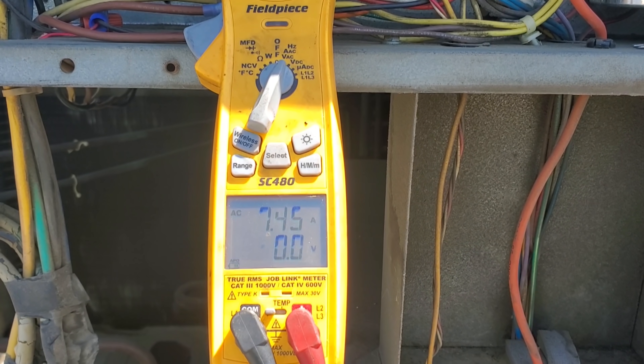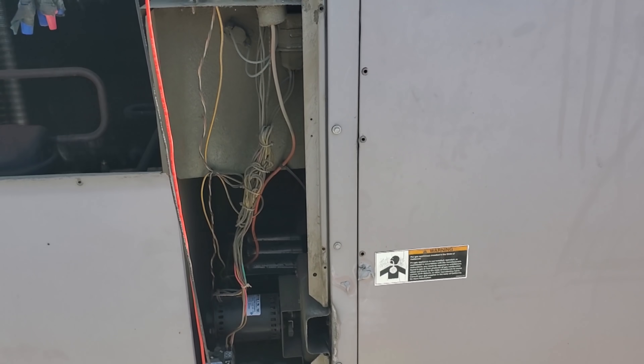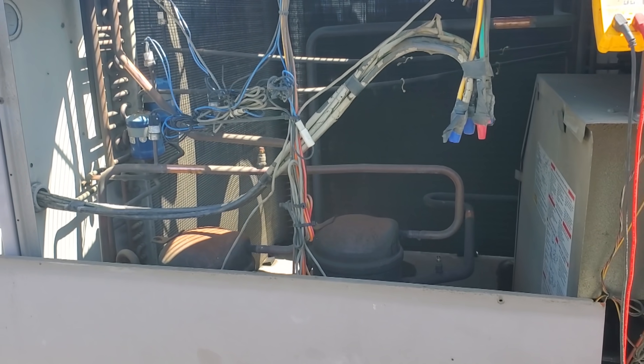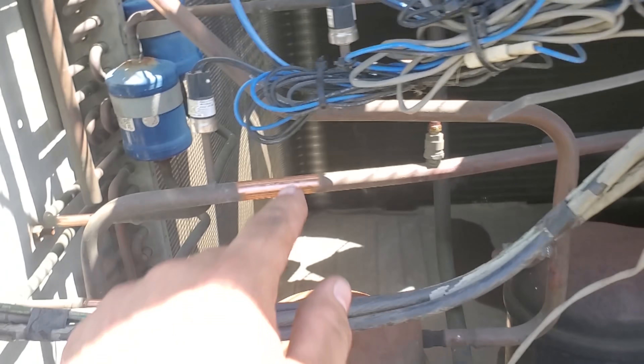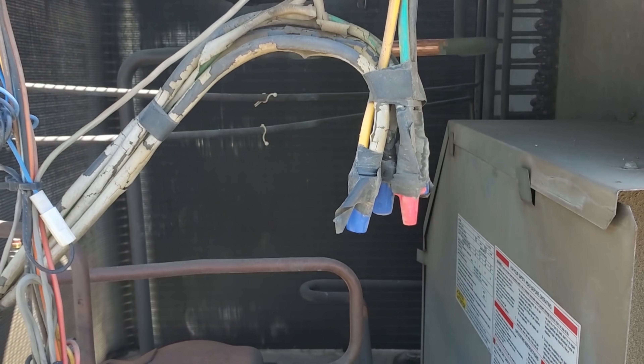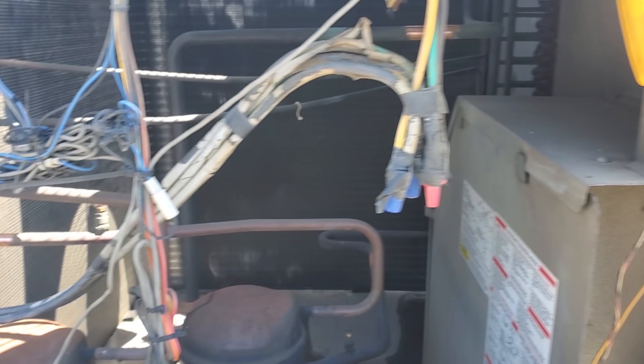Now we're undercurrent. We're allowed to run 7.5 amps and we're good. We're going to fire up the cooling. I got to figure out what I got to do — I probably got to log into their internet thermostat, fire up the cooling, and we're going to proceed to check first and second stage. I guarantee they're going to be low on charge because those caps are missing. I went ahead and sanded up the line set clamps because I use the Fieldpiece Job Link probes with the Rapid Rail technology — they got to have clean copper for it. So I cleaned that up while I was waiting.